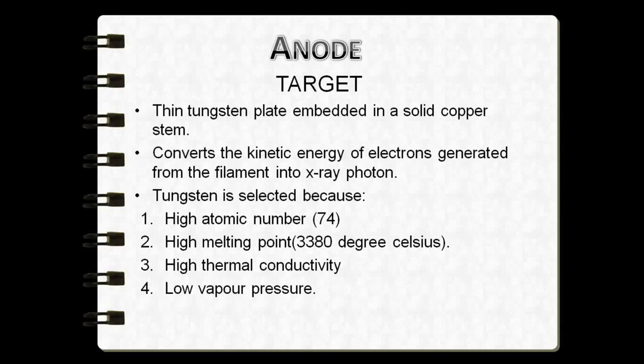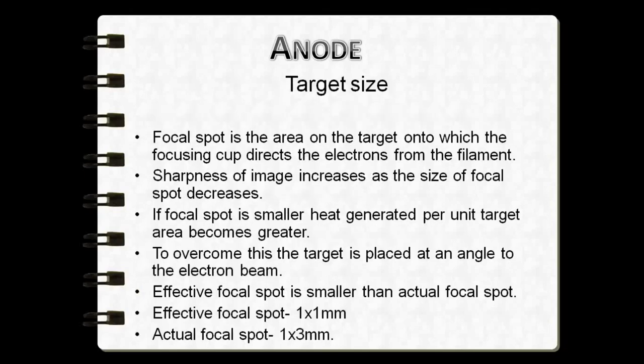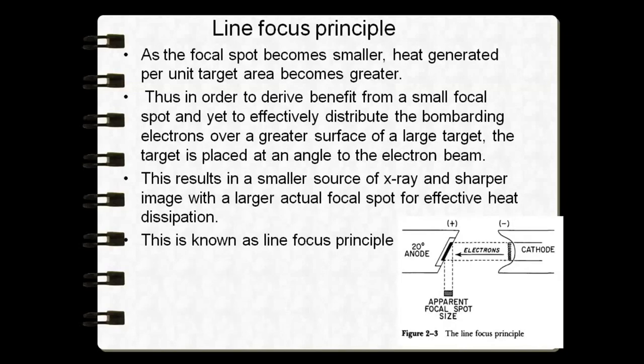The target converts the kinetic energy of electrons generated from the filament into x-ray photons. The electrons hit a specific area within the target called the focal spot. As the size of the focal spot decreases, image sharpness increases. To achieve a smaller focal spot, we follow the line focus principle — also called the Benson line focus principle — which states that we need a smaller focal spot size while generating heat over a wide area of the target.